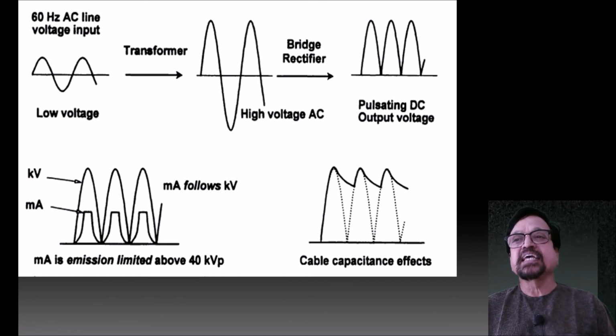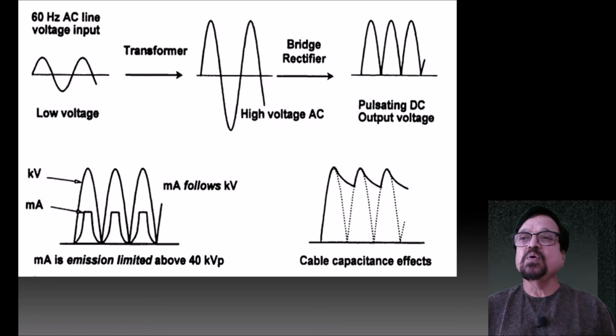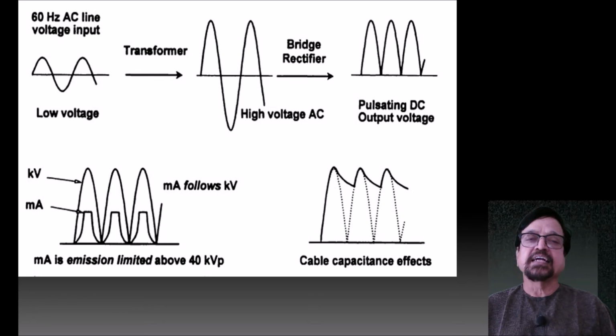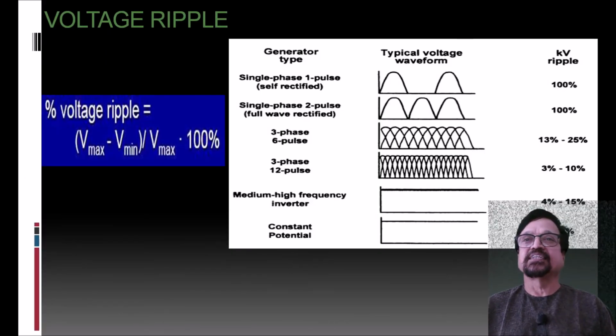Now when it passes, it goes to a rectifier, and what the rectifier has done is the negative side is converted into a positive side, so it is full rectification. That is how a single directional flow is achieved to the tube of desired requirement. It has got a high voltage, and it has got a unidirectional flow with the help of the diode and rectifiers.